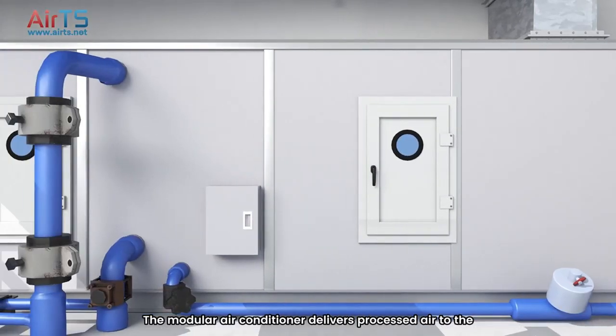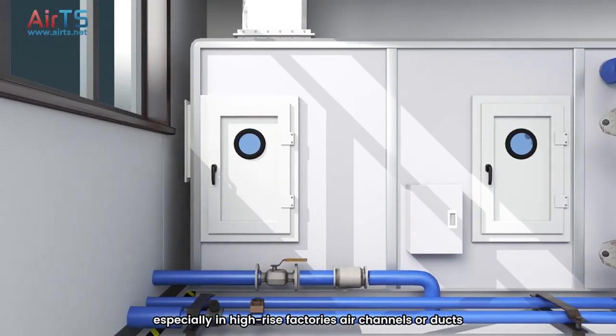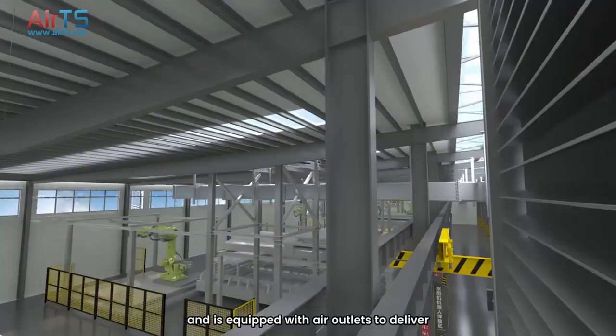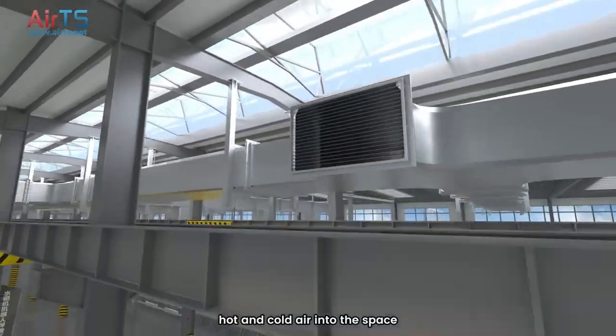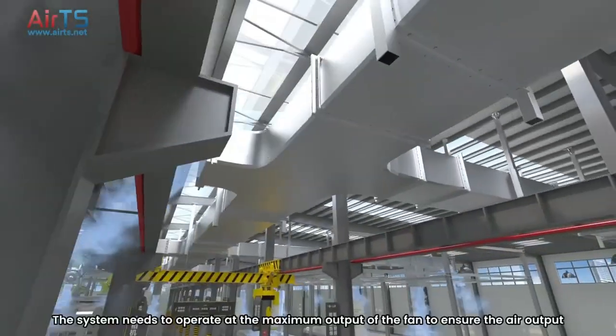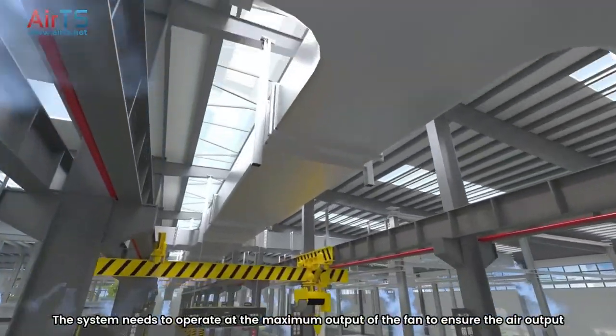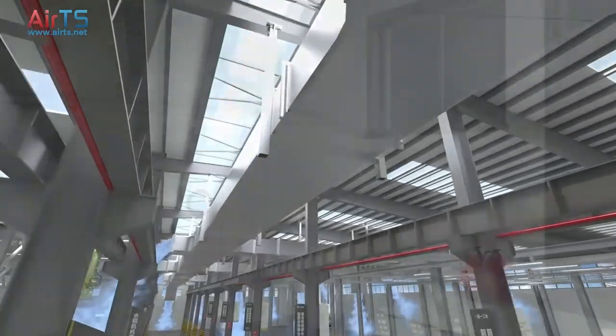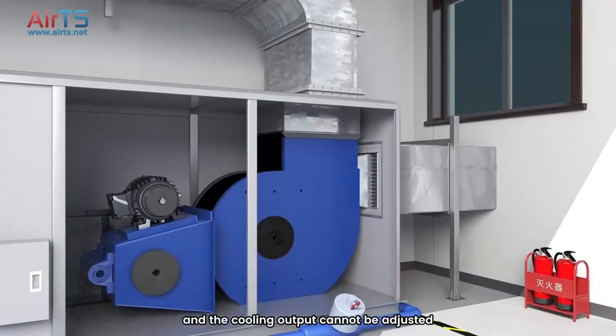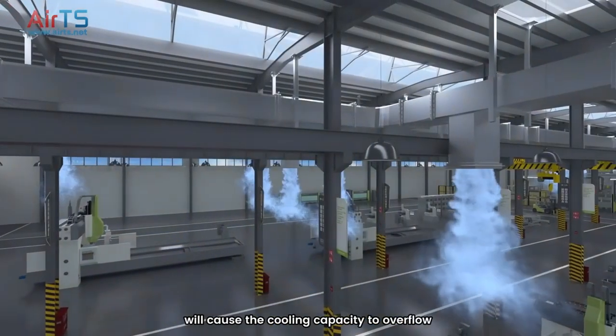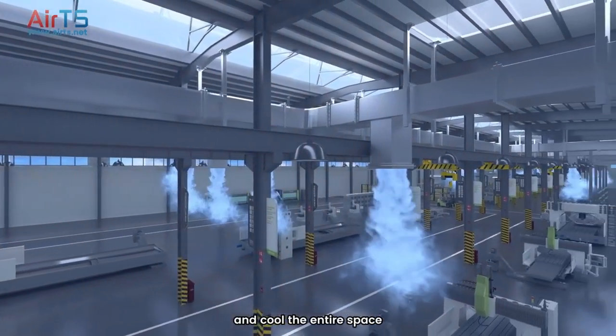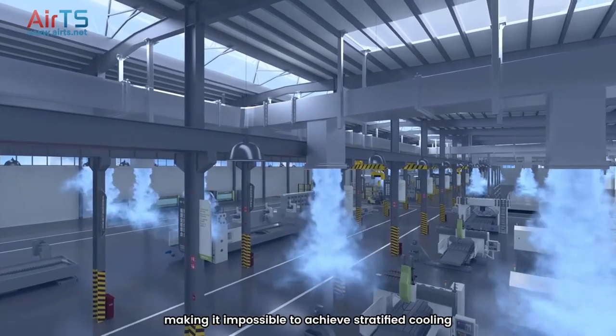The modular air conditioner delivers processed air to the entire building through air channels or ducts, and is equipped with air outlets to deliver hot and cold air into the space. The system needs to operate at the maximum output of the fan to ensure the air output, and the cooling output cannot be adjusted. Running at full load for a long time will cause the cooling capacity to overflow and cool the entire space, making it impossible to achieve stratified cooling.